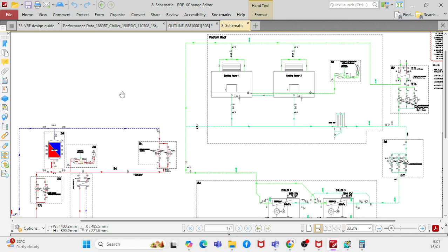This is not like a chiller. But I have a question here. Say for each cooling tower you have three pumps: two duty and one standby, right? What is the reasoning for the two duty? Can I not just make it one duty and one standby? Yeah, you can make it, no problem. But why do you make multiple duty pumps?